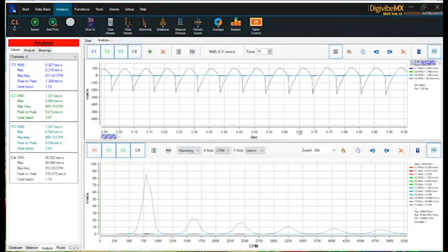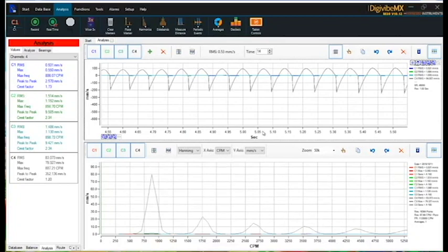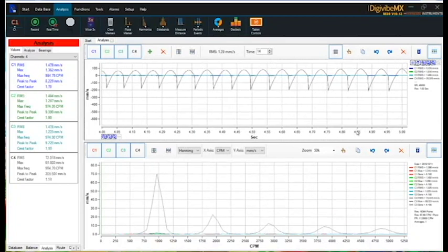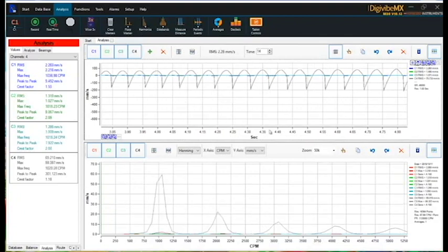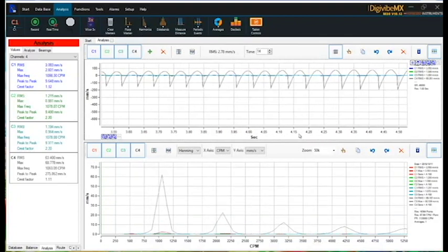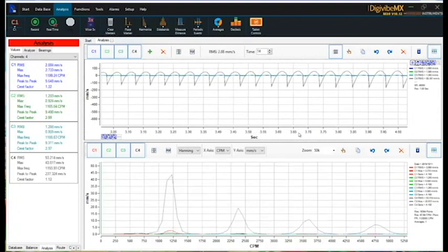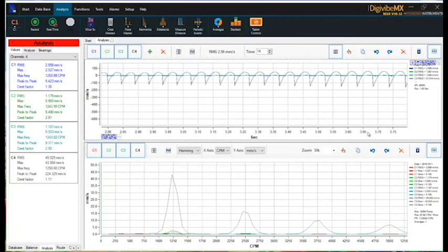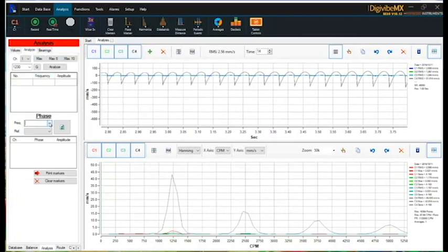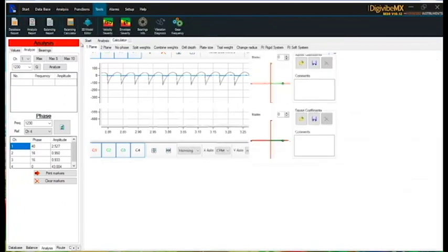So let's find first the speed. So here, if I scroll, I will see that the FFT is changing. So let's adjust it to 1200 RPM. There. So now we select the speed to which we want to set the phase, and then channel 4, in the 4 channel interface, channel 4 is the optical sensor. See, so this is going to be the reference.